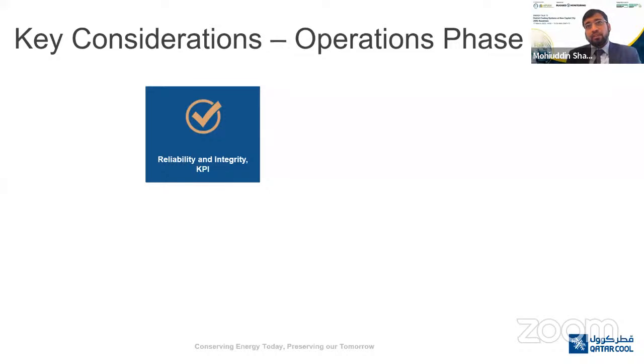If not, Qatarcool follows a condition-based monitoring strategy. Our plants have online vibration monitoring of all critical plant items like the chillers, the pumps, and the cooling tower motors, to catch any issues well in advance before they fail.